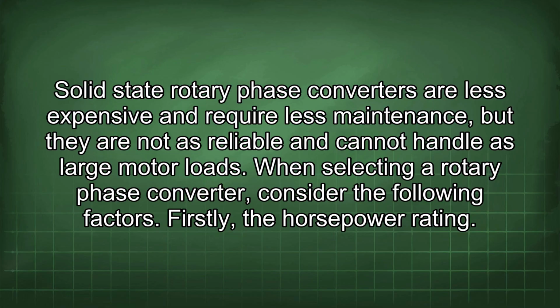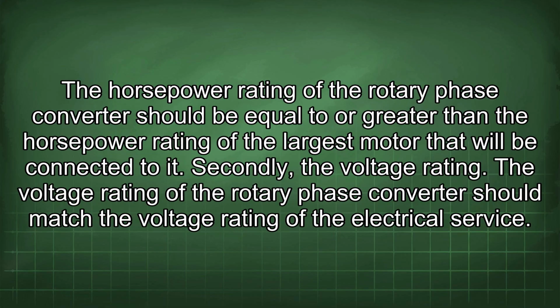as large motor loads. When selecting a rotary phase converter, consider the following factors. Firstly, the horsepower rating. The horsepower rating of the rotary phase converter should be equal to or greater than the horsepower rating of the largest motor that will be connected to it.